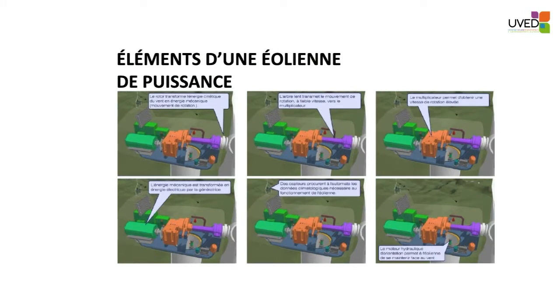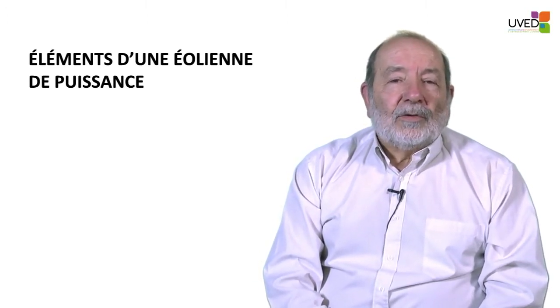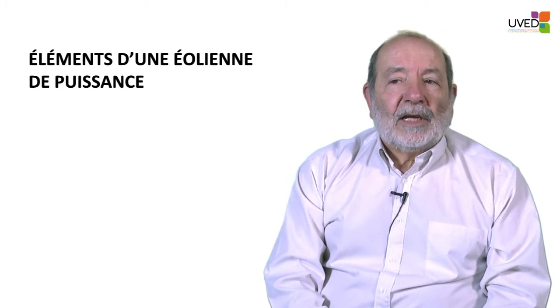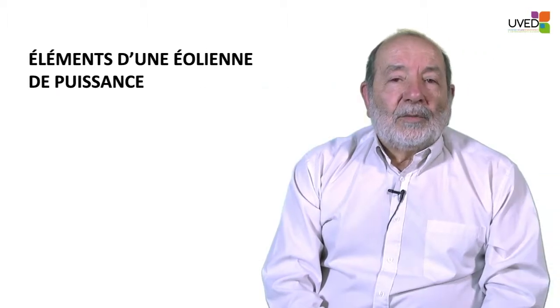Why a gearbox? Because the rotor rotates at approximately 20 to 30 revolutions per minute. At the output of the gearbox, the speed will be 1,500 revolutions per minute, which is compatible with the asynchronous generator that turns mechanical energy into electrical power.